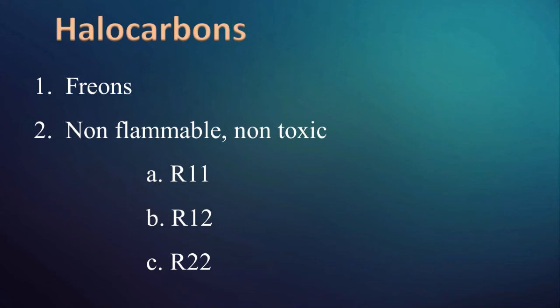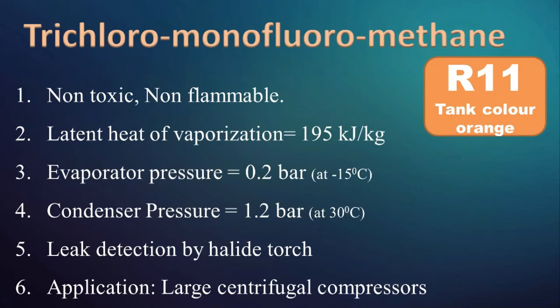Let us see some Freons used in the HVAC industry. R11, Trichloromonofluoromethane, is a non-flammable, non-toxic compound. Evaporation pressure is 0.2 bar at minus 15 degree Celsius, whereas condenser pressure is 1.2 bar at 30 degree Celsius. Latent heat of vaporization of R11 is 195 kJ/kg. Leak detection of R11 is done by using a Halide torch. It is used for flushing of systems and finds applications in large centrifugal compressors.